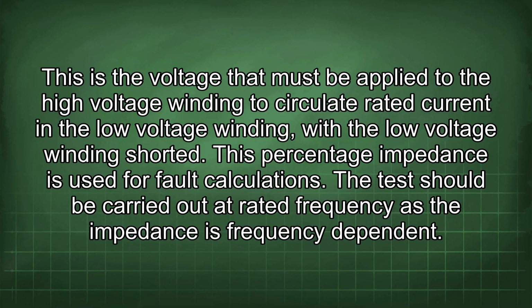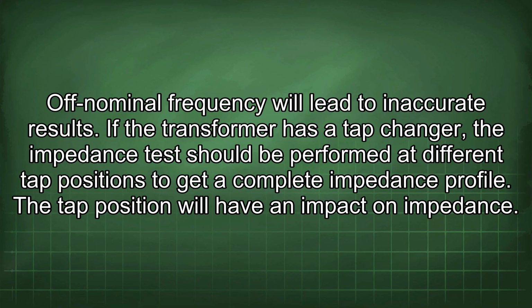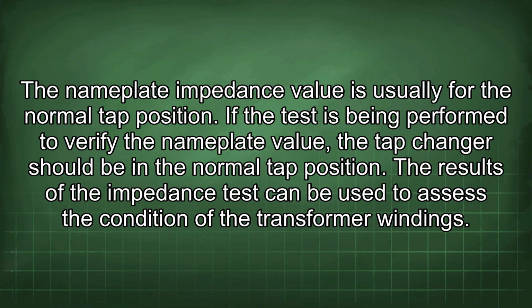This percentage impedance is used for fault calculations. The test should be carried out at rated frequency, as the impedance is frequency dependent. Off-nominal frequency will lead to inaccurate results. If the transformer has a tap changer, the impedance test should be performed at different tap positions to get a complete impedance profile. The tap position will have an impact on impedance. The nameplate impedance value is usually for the normal tap position.